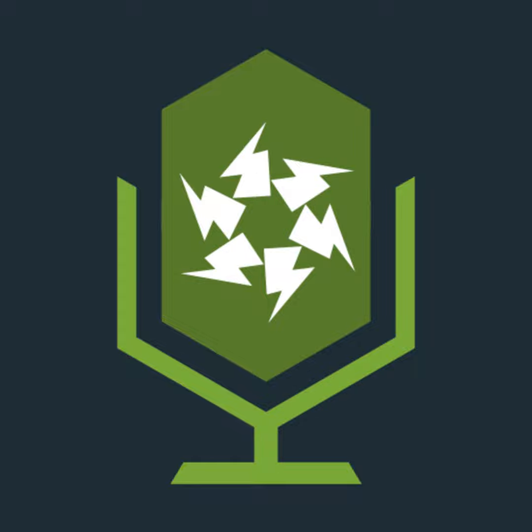The question then is, what's my earthing system? If my earthing system is a TN system, then I am 0.4 seconds. If my earthing system is a TT system, 0.2 seconds. We're sticking with AC for this. Alright? So, that seemed fairly easy, but we are going to repeat that a lot later on when we start looking at cable selection, because we'll say, okay, we have this cable type, and how many amps is required to disconnect it. That will always be determined by this part, which tells us the maximum required disconnection time.